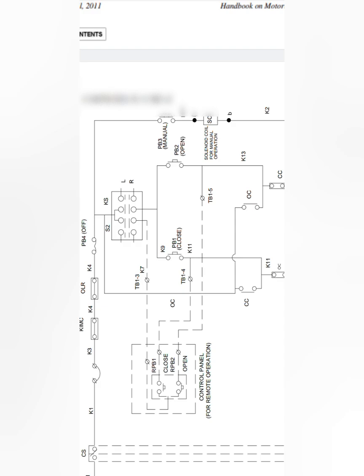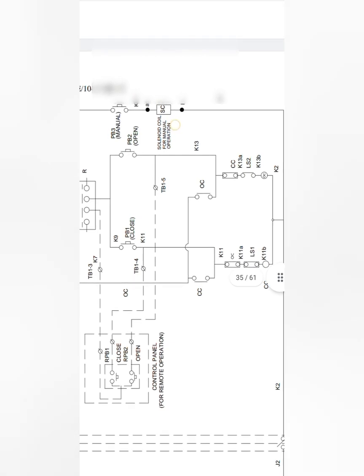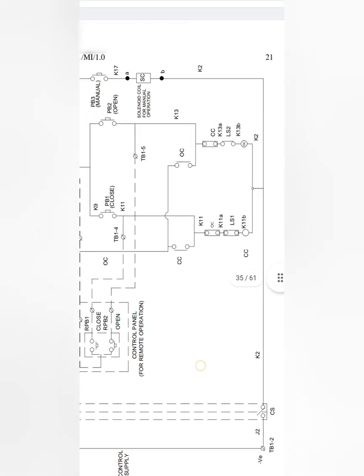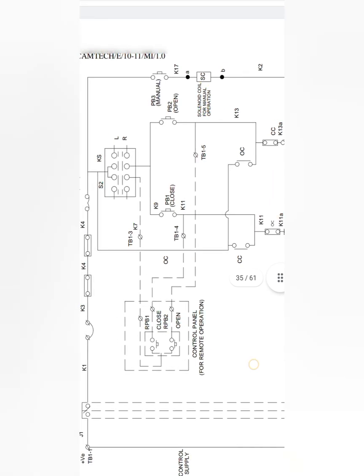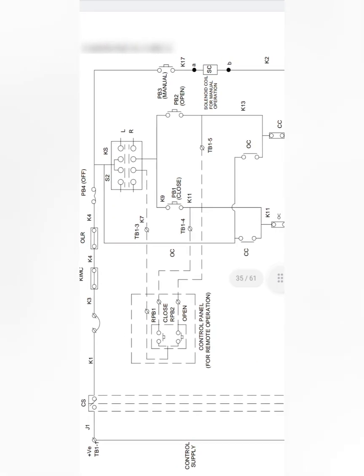The third one is your solenoid coil, which is for manual operation. If manual operation needs to be carried out mechanically, the solenoid coil will be connected with your key interlocking systems. If we push this manual push button PB3, automatically your solenoid coil gets energized, and then from that solenoid coil we can remove the key interlocking keys. We then need to fix those keys in your mechanical operator box, and then only we can do the mechanical operation.